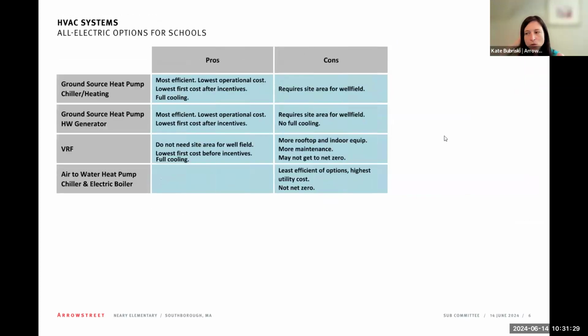So these are just some high level pros and cons. We've talked about some of them already. On the ground source heat pump side, it is the most efficient system, so we have the lowest EUI, lowest energy used. It's also the lowest operational cost on the utility side in terms of not needing as much energy, but also on the operation and maintenance side, compared to say the VRF system, which has a lot more equipment and things that need to be maintained throughout the building. It will be the lowest first cost after incentives, and we'll talk about the incentives. And it has full cooling.